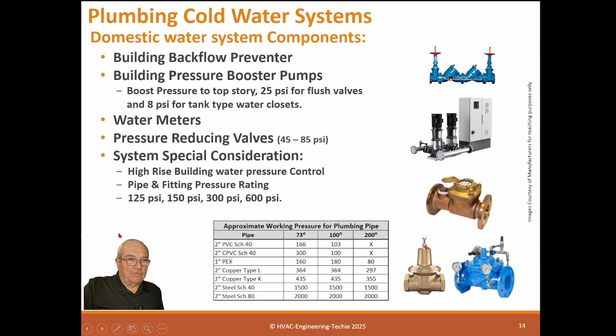But look at 200 degrees. If you've got hot water, no PVC, 1-inch PEX, only 80 psi. 2-inch copper, 297. 2-inch copper type K, 355. But for steel, that temperature is no concern. For plastic pipes, though, temperature is a problem. We have to be careful we don't exceed those parameters.